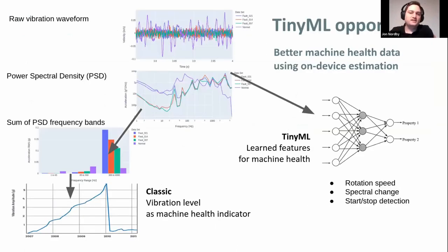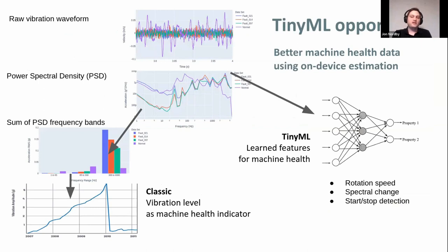This system uses a classic DSP architecture to extract vibration levels, which is already a very useful indicator of machine health, as the examples show. However, it's known from vibration monitoring literature that there are many more advanced ways of analyzing vibration data that can give an even better estimate of machine health. Running TinyML models on devices is key to doing this in an efficient way. We have now started to test this out — for example, to estimate the rotation speed, the number of starts and stops, as well as changes in the frequency spectrum of the vibration signature.